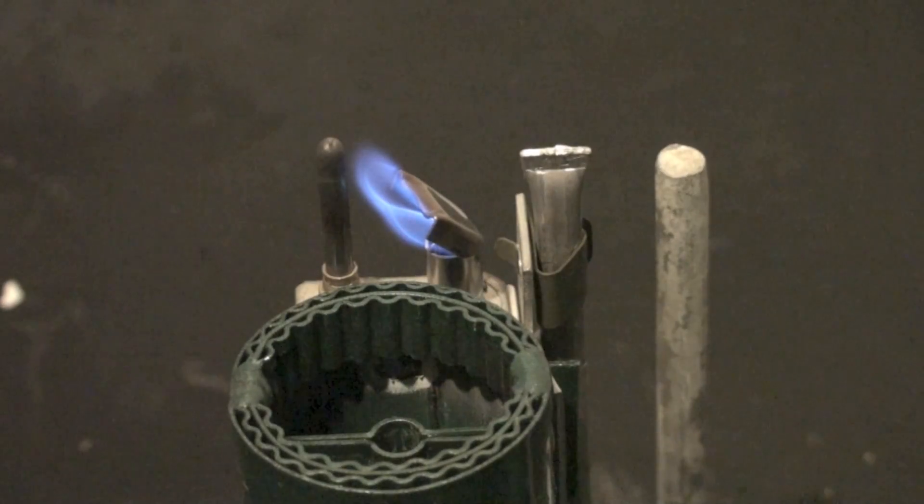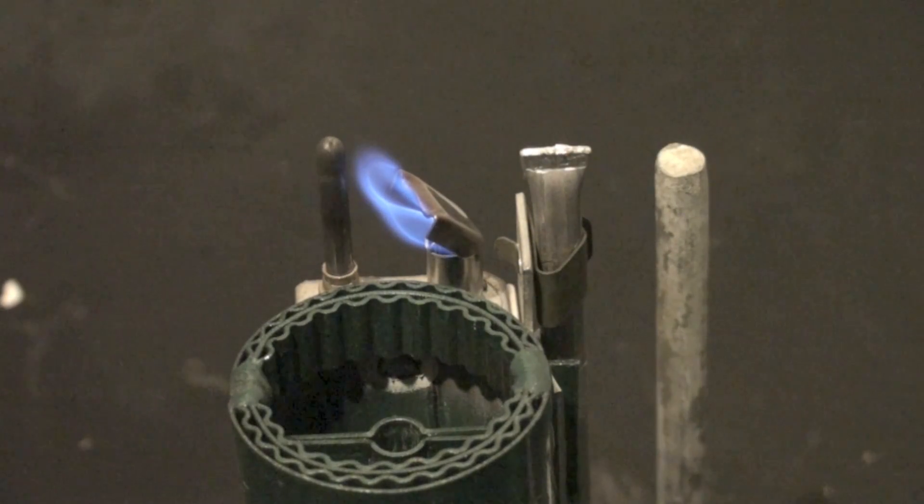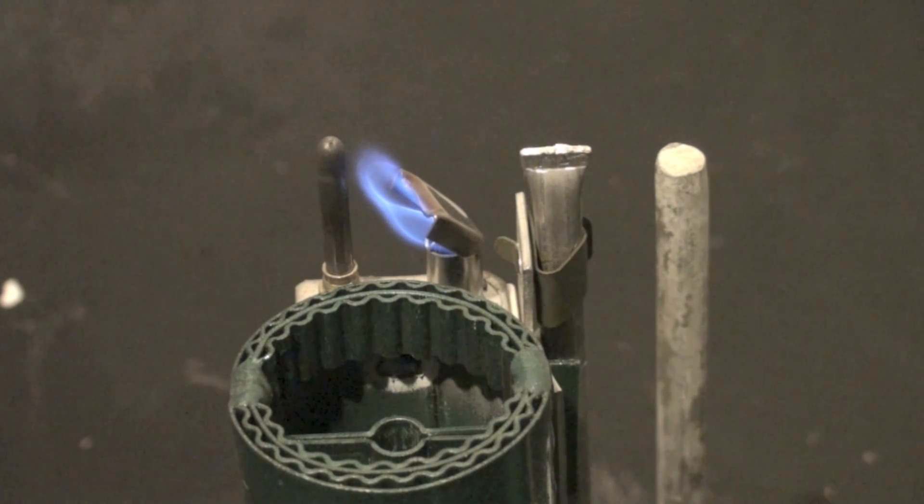Okay, let's look at what's wrong with this pilot. You can see the pilot is there. However, it's not even reaching the thermocouple. And it may work for a while this way, but probably not for a long time. Eventually, it's going to move away a little bit from that thermocouple and drop it out. Or just go out itself.